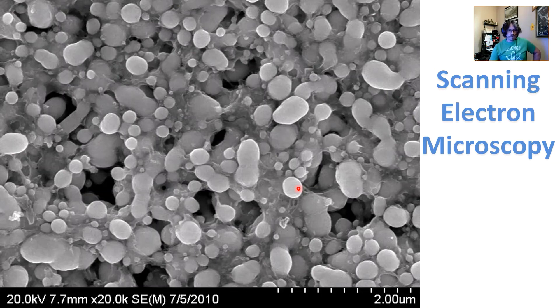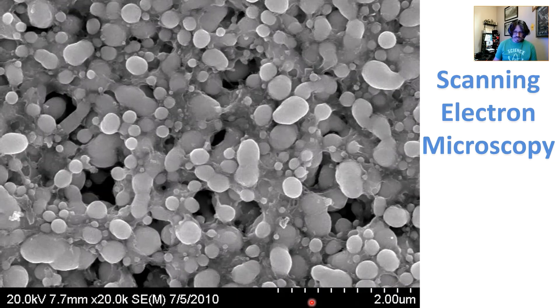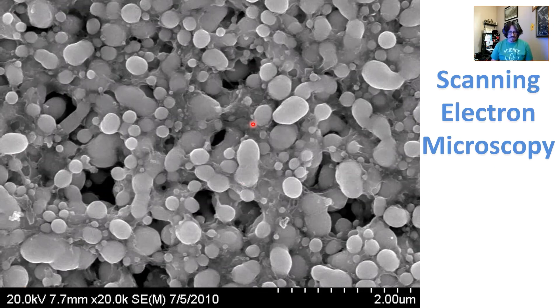Some interesting items to notice when you look at a micrograph: the magnification only applies to the original print magnification, so the micron marker is by far the most important piece of information — it allows you to turn qualitative information into quantitative. The accelerating voltage is generally listed on the micrograph; 20 kilovolts was used here on this field emission microscope. Working distance is the distance between the objective aperture and your specimen — you typically want a shorter working distance for higher magnification imaging.